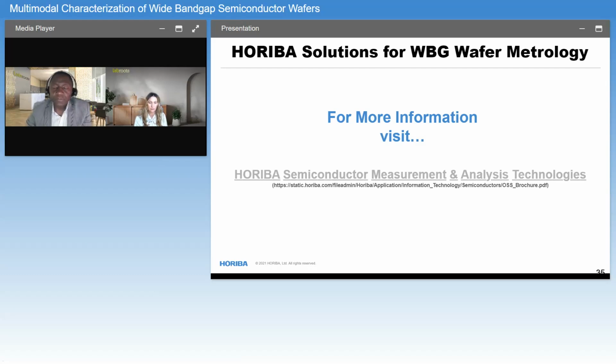Absolutely. And I did not mention this in the last part of the presentation that talks about the challenges. Definitely for wide bandgap materials, one of the challenges is dealing with systems that have this UV excitation for two reasons. One is that pretty much everything is absorbing in the UV, so the optics and the conveyance mechanisms for UV have to be specifically designed, and that is the case for our systems. And of course, UV radiation by itself can also be hazardous, and so the systems have to be special in a way.